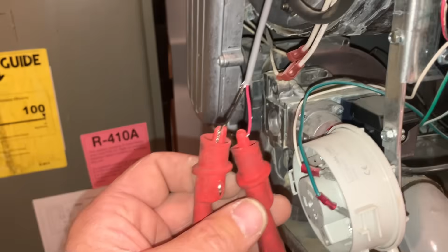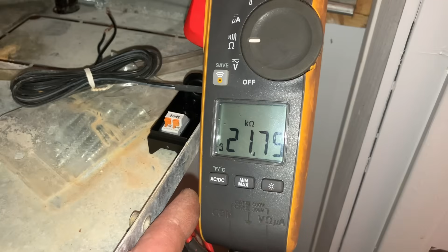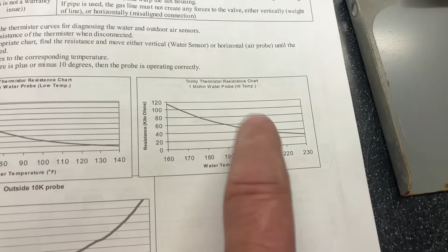All right, we're checking resistance on that water temperature sensor. I cut the wire and I'm reading 21.6 ohms. So this is in K ohms, right? Resistance 21 right there. It thinks it's that temperature, but it's not. So we have a bad thermistor because it's not 200 something degrees. It's more like 80.